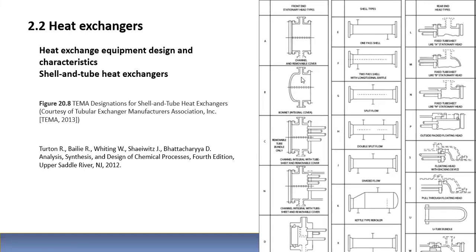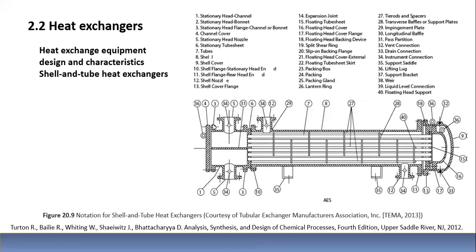Usted puede ver la tapa. La tapa aquí también es apernada. Se aperna con esta sección y esta sección se aperna con la carcasa. En la carcasa están soldados el espejo y los tubos, como usted puede ver aquí. No en este cabezal. Este cabezal se puede desapernar y sacarlo del todo. Y eso sirve si usted quiere limpiar interiormente los tubos pasando un cepillo de tubo en tubo, en caso que tenga algún tipo de depósito orgánico.